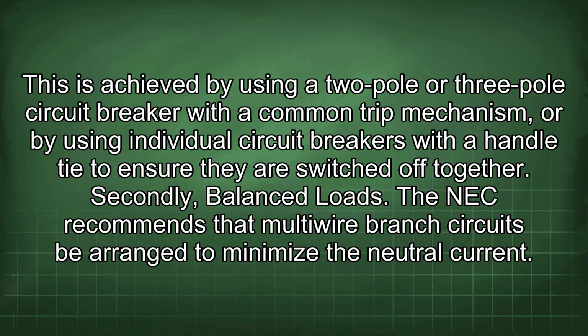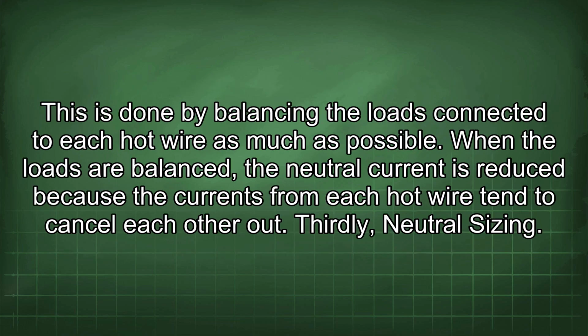Secondly, balanced loads. The NEC recommends that multiwire branch circuits be arranged to minimize the neutral current. This is done by balancing the loads connected to each hot wire as much as possible. When the loads are balanced, the neutral current is reduced because the currents from each hot wire tend to cancel each other out. Thirdly, neutral sizing.